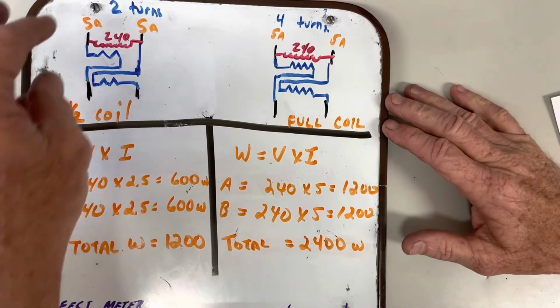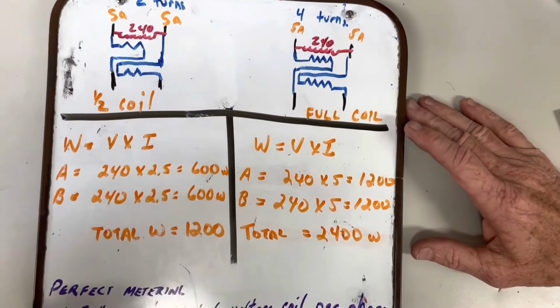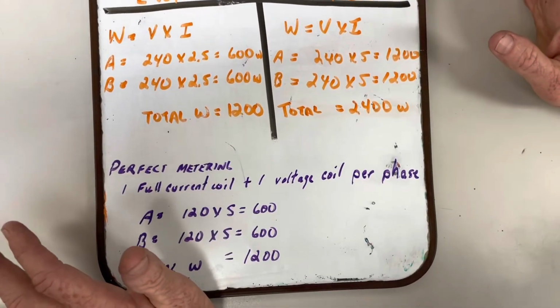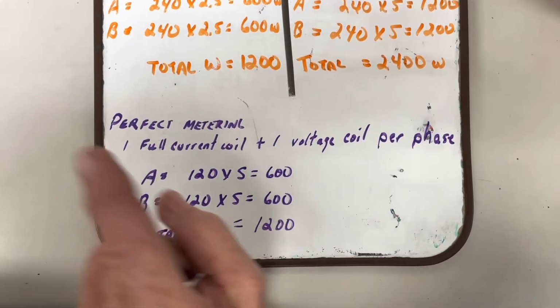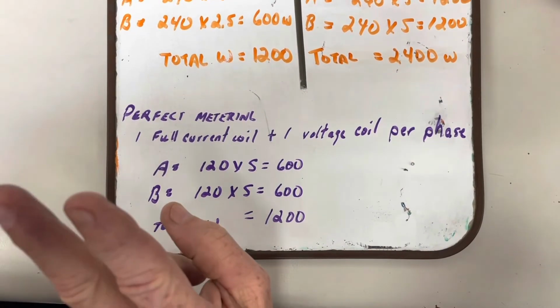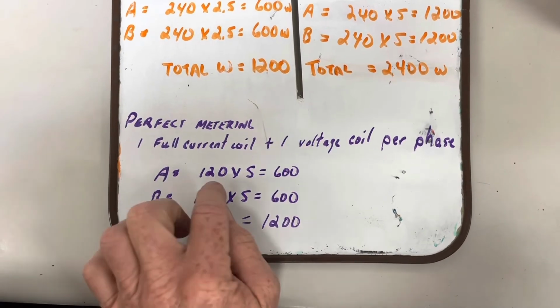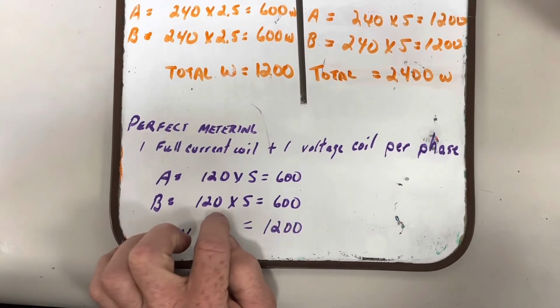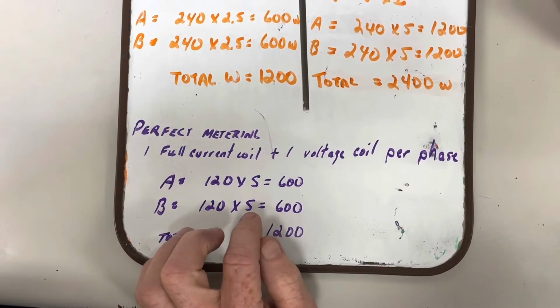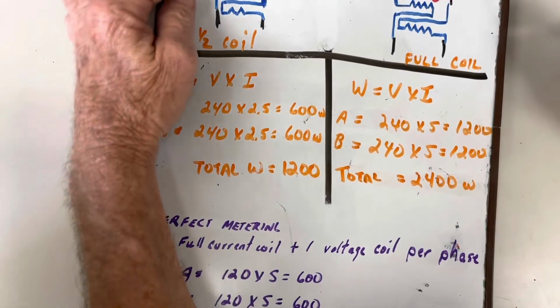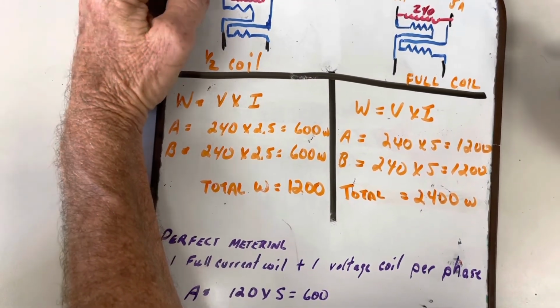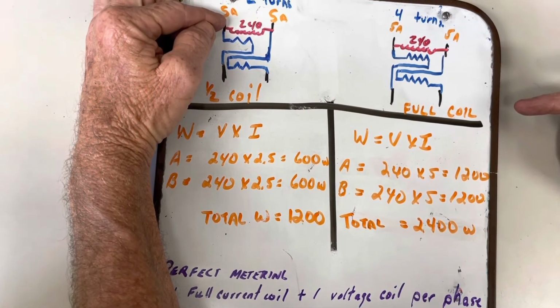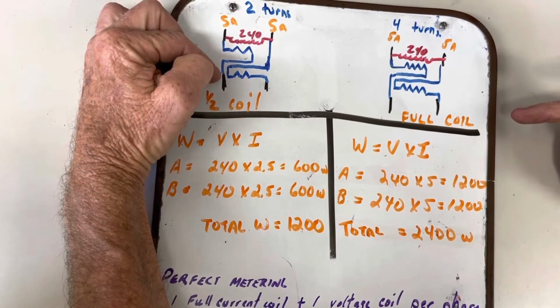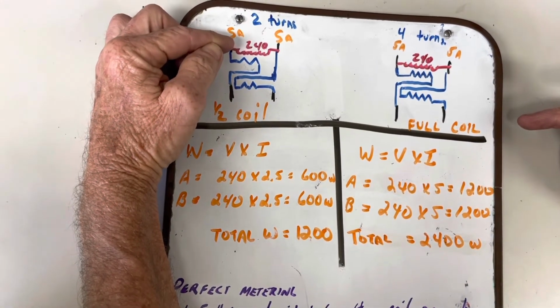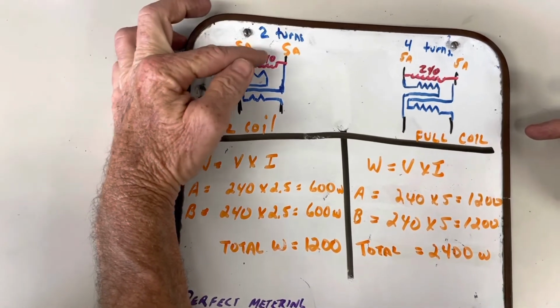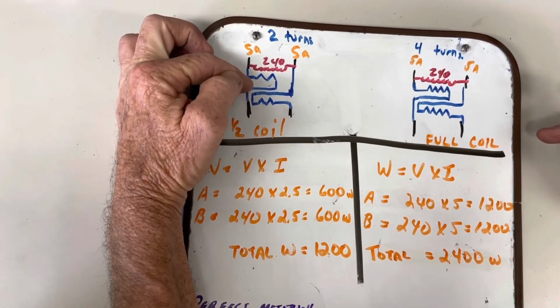So to prove why we are using half the turns, I'm gonna go to a perfect scenario in perfect metering where we use 1 full current coil and 1 voltage coil per phase. And when we do that, we're using phase to ground, so we get 120 volts for A times 5 with 600 watts, and 120 times 5 with 600 watts, we get 1200 watts. And the reason we're splitting this current coil in half is because we're using 240 volts. Well, you and I know that each phase to ground should be only 120 volts to measure times current for an imbalance. So to justify using one coil, we have to take the current coil and split it in half.